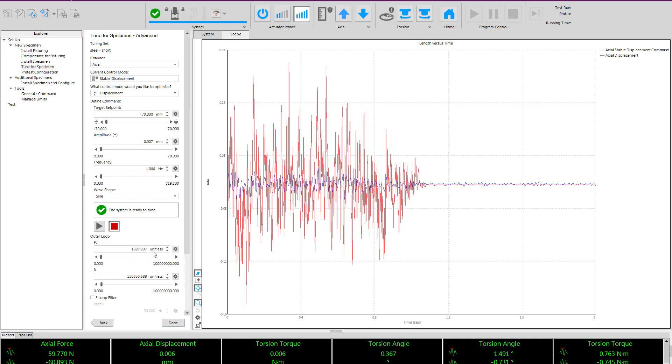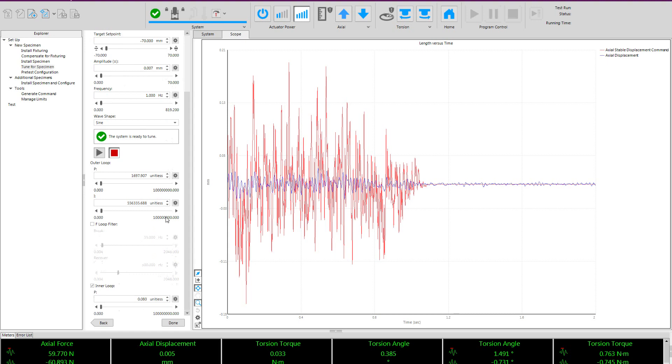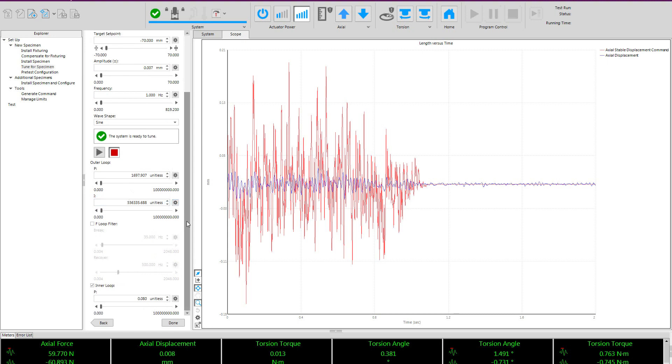Beyond that, you can go to the advanced tab, which allows complete access to the complete tuning values, PID, proportional integral and derivative gains for the system.